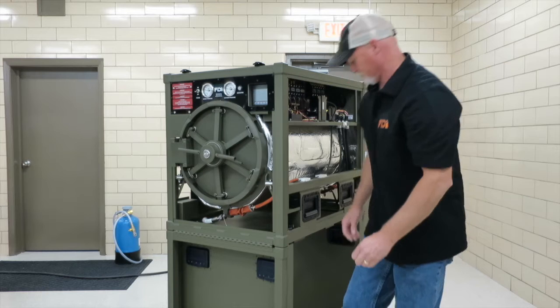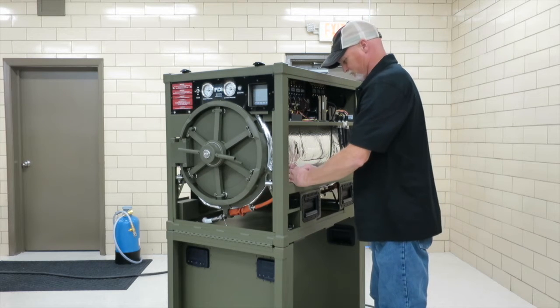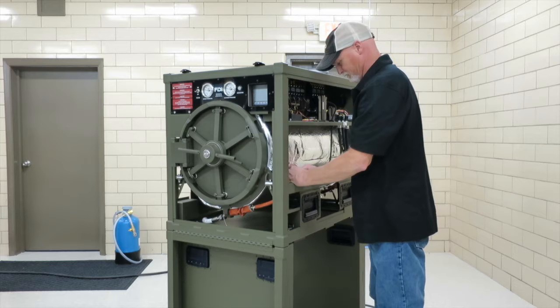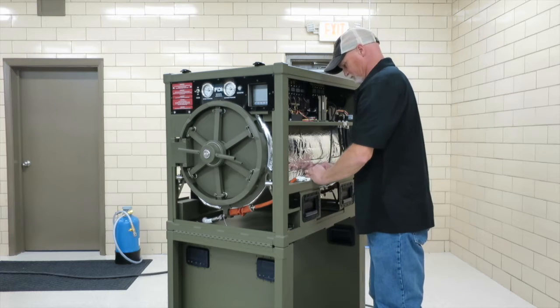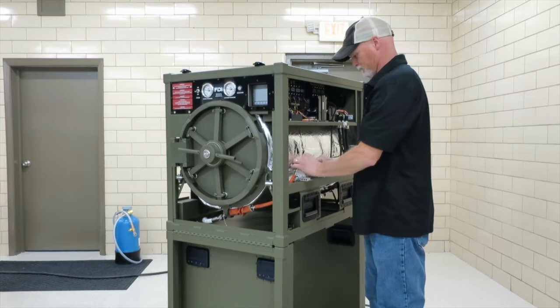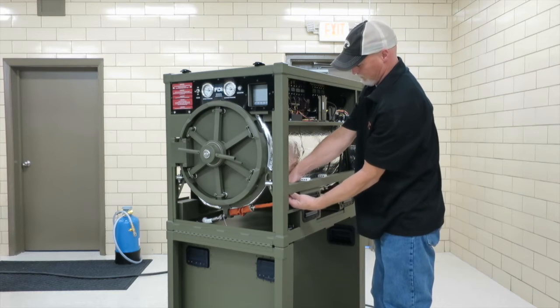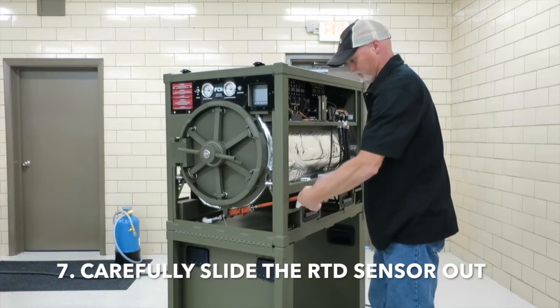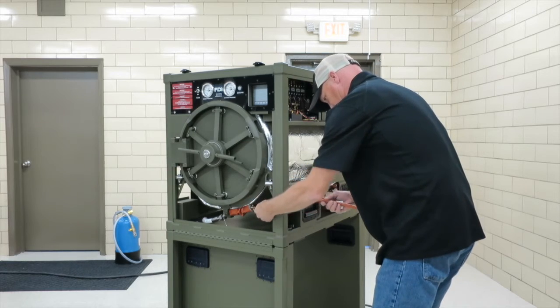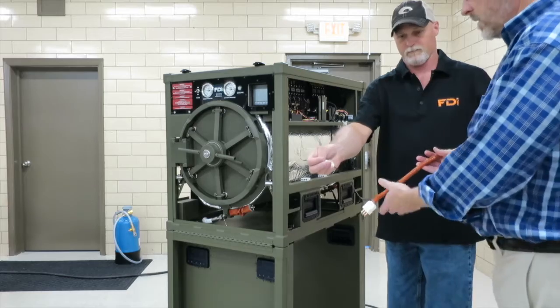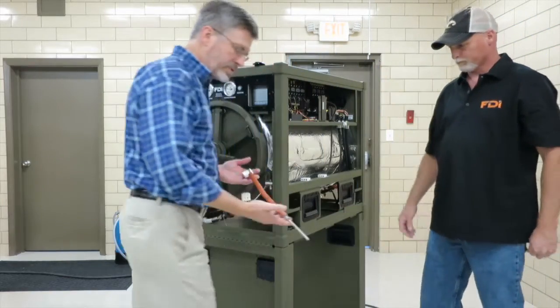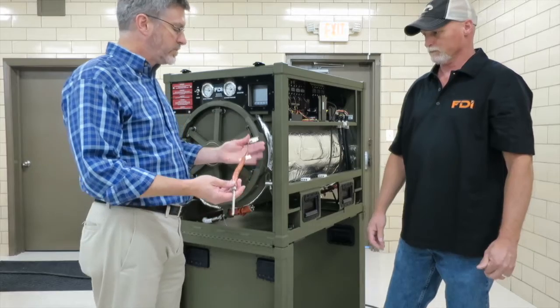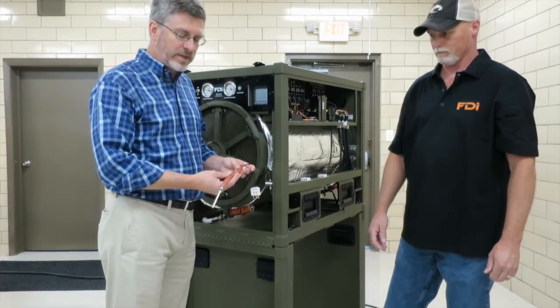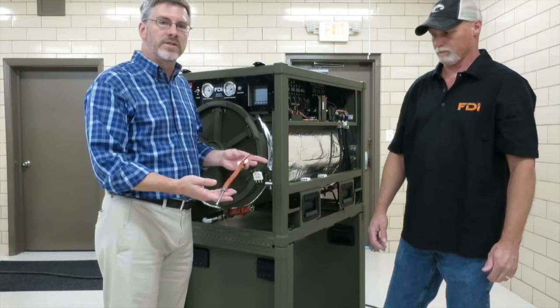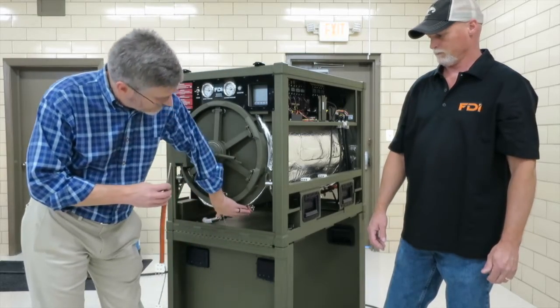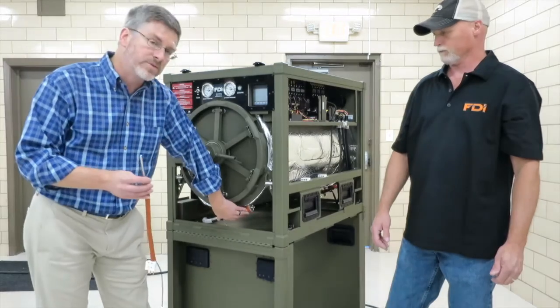Okay, so once the screws are out, you can just slide the connectors apart. And just gently pull the probe out of the tubing. Okay, so you can see this will be the spare part that you'll get. So you get connectors, right length. You get the probe. You get this insulation sleeve with it. So this is what you'll see as a spare part. You want to make sure that this sleeve stays on. That's not part of the spare part.